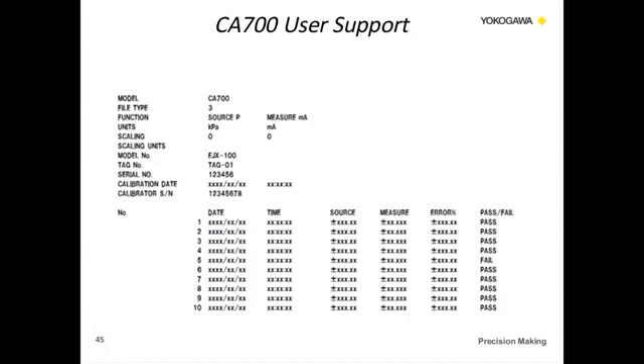Again, this goes back to the previous screen where we entered that information in. The tag number, the serial number. It'll also give you the calibration date and time. Also, the serial number of the calibrator you used. So this will give you a lot of data there in terms of the different steps and the error percentage and whether or not it's a pass-fail. So again, the pass-fail will be a function of the error percentage that you set up.